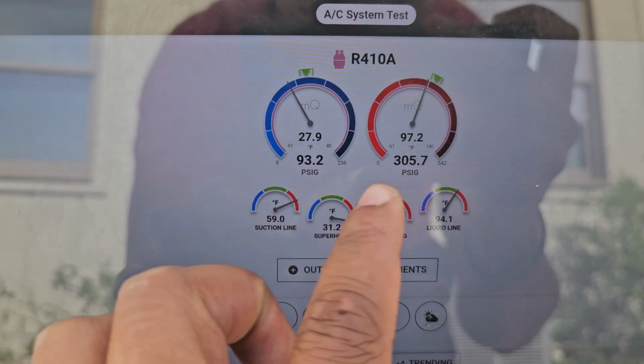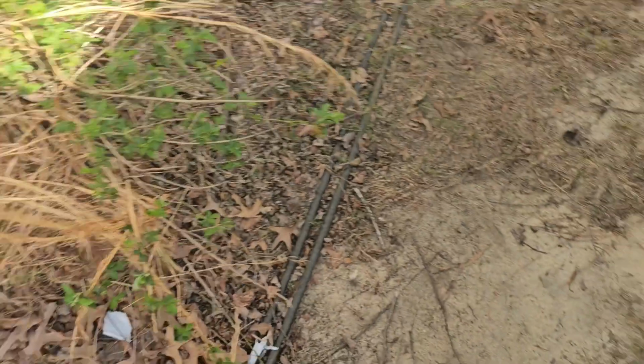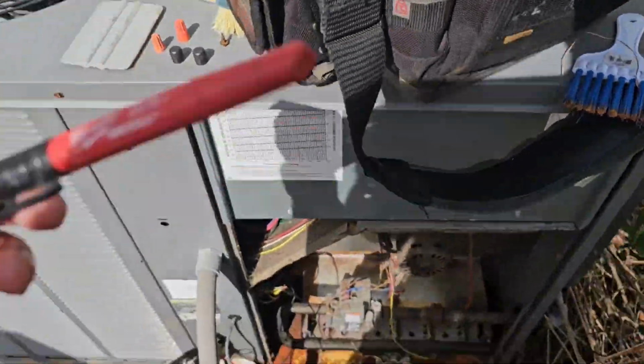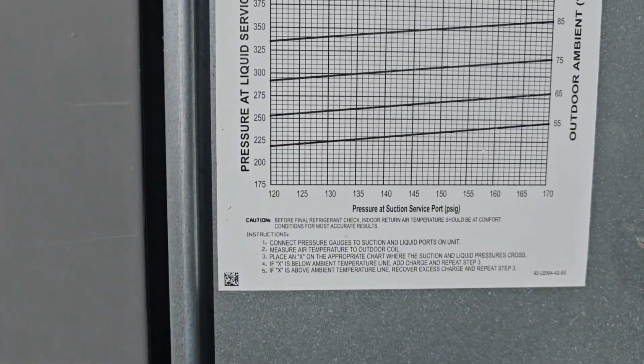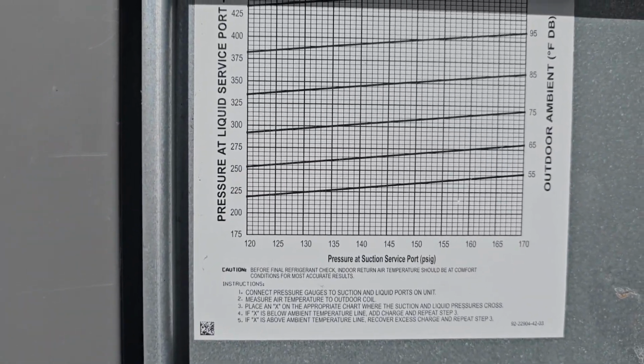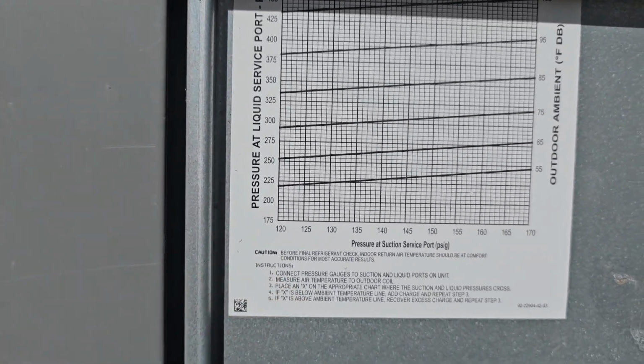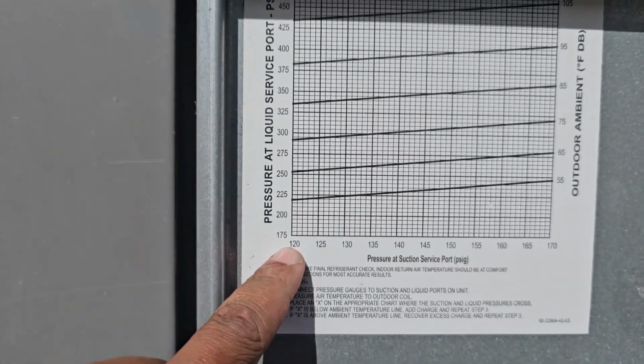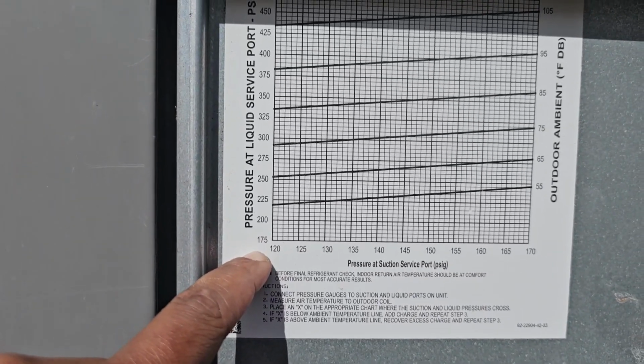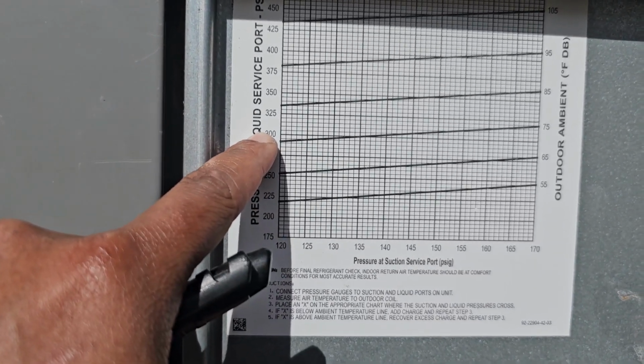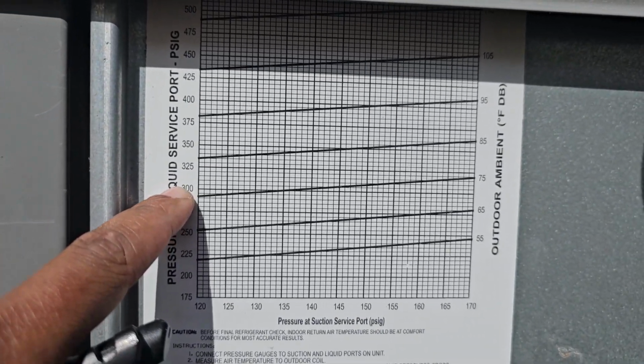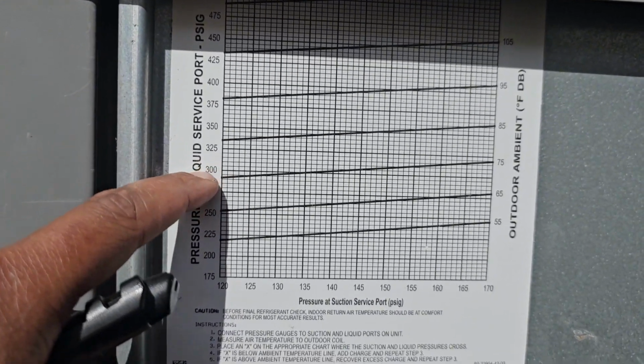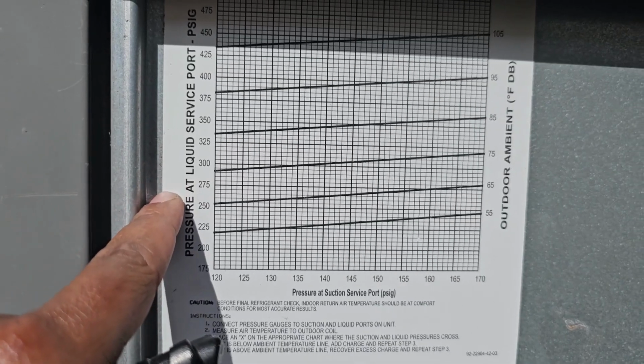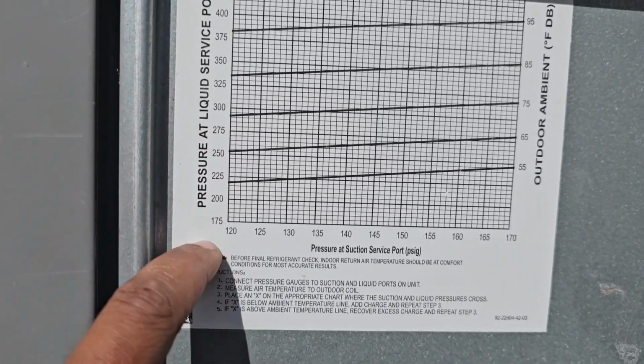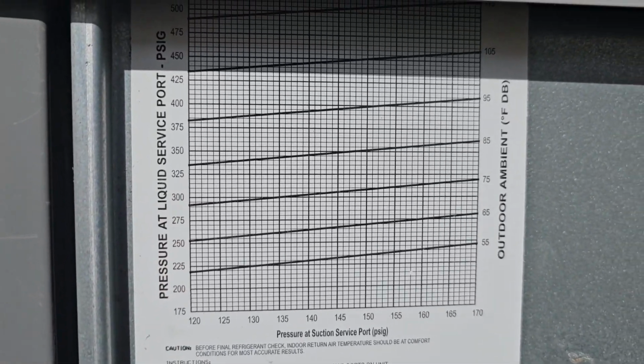You know what, okay, let's try something else. So we were reading 93 at 305. Let's see what the chart right here says. Sorry if the fan motor's messing with the wind. The 93 measurement isn't even on here, so 93 and 305 up here, and we're like 80 something degrees. So I do think we'd be like way over here, low. Judging by this chart, we're low.